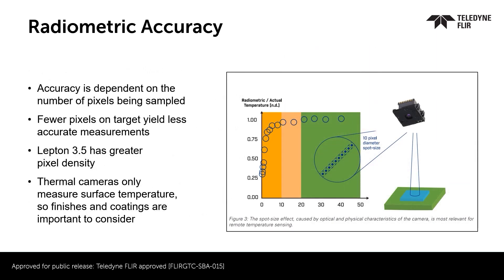Radiometric accuracy is also dependent on the number of pixels that are on the target being measured. 5 pixels is the minimum, and 10 or more pixels on a target is best. The target being measured should also be uniform temperature. The smaller the target, the closer the camera must be to ensure enough pixels on target. With more pixels and greater resolution, Lepton 3.5 is the preferred choice for measuring surface temperature.